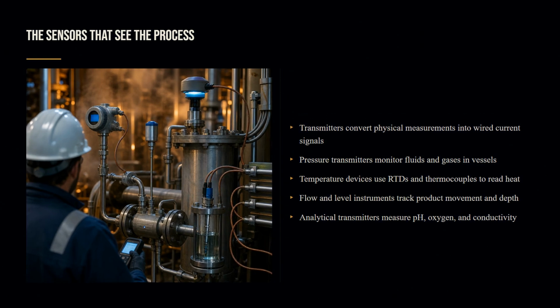Field transmitters convert physical measurements into current signals sent over wire to the controller. Unlike the wireless variety, these devices send data on a conductor, not through the air. Pressure transmitters measure fluid and gas pressure in pipes and vessels. Temperature transmitters use RTDs, resistance temperature detectors, and thermocouples to read heat. Flow meters, magnetic, ultrasonic, and Coriolis types, measure how much product moves through a line. Level transmitters using radar or ultrasonic technology measure liquid depth in tanks. Analytical transmitters measure chemical properties: pH, dissolved oxygen, conductivity.